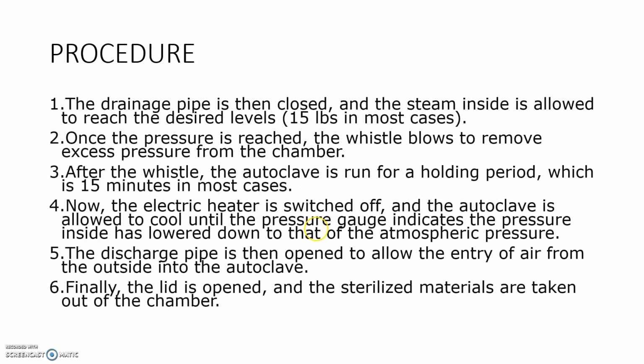Then we close the drainage pipe and we allow the steam to increase inside until it reaches the desired level, that is 15 psi in most cases. Once the pressure is reached, the whistle starts blowing to remove excess pressure from the chamber. After the whistle, the autoclave is run for a holding period of 15 minutes. Now after the 15 minutes, we switch off the electrical heater and allow the autoclave to cool until the pressure gauge indicates the pressure inside has lowered to that of the atmospheric pressure.